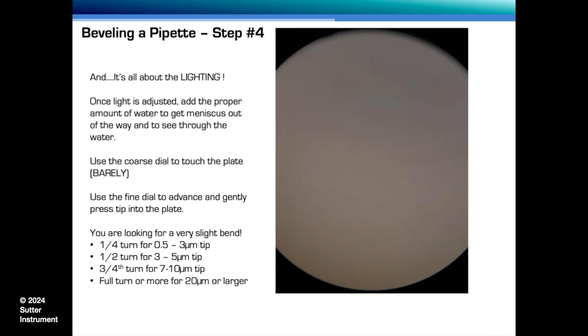And then for tips that are over 20 microns or larger, you're going to need to, again, trim it back, and then you're going to do usually 1 full turn, maybe 2 or 3 if the tip is really large. This is the fine dial, and you can see I've marked it, and I've put the tip sizes there just as a reference. But usually I have that front mark there where it says 20 microns. I have that front mark there all the time, so I know how many parts of a rotation or full rotation I've taken. And then here is a video showing the pipette.